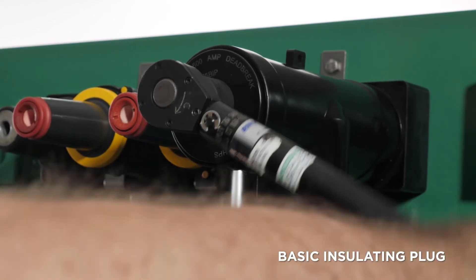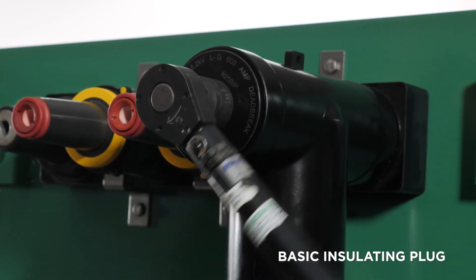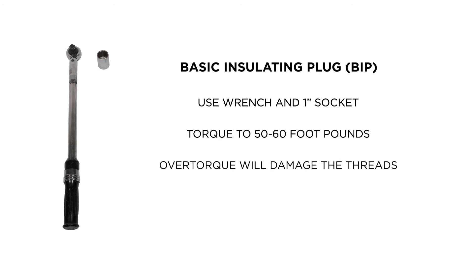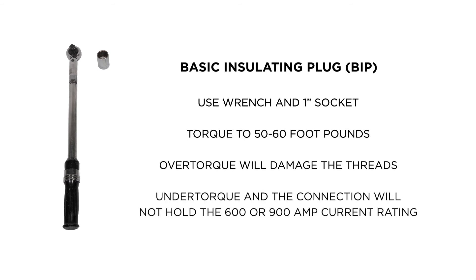The basic insulating plug, or BIP, has a 1-inch hex nut for tightening. A torque wrench and 1-inch socket is required to torque the BIP to 50 to 60 foot-pounds. Remember, overtorque will damage the threads of the aluminum or copper stud, and the connection will not hold the 600 or 900 amp current rating.